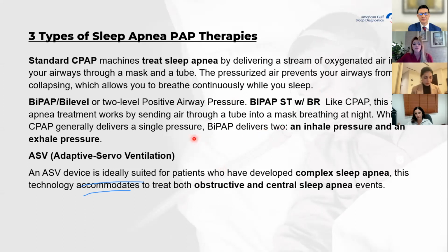On our bilevel and BiPAP, you have two types of positive airway pressure, where you're breathing in a certain amount of air and you're breathing out. So the IPAP is, say, at 18 centimeters of water pressure, and you're going to breathe out against 14 to 15 centimeters of water pressure. And then they also have the BiPAP ST with the backup rate. This is like the CPAP machine, where the treatment works by sending air through a tube. The same, it generally delivers two different pressures. As I said, you're breathing in and exhaling against two different pressures. And unlike the CPAP, which is generally just a standard single pressure.